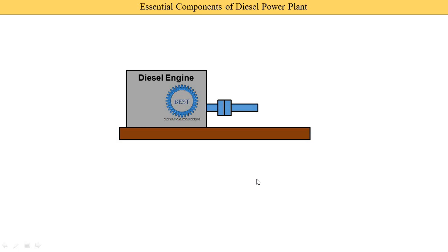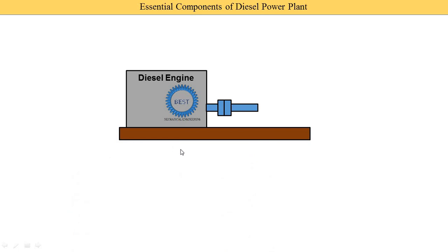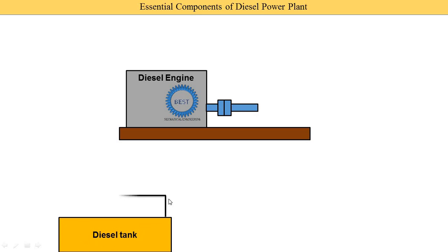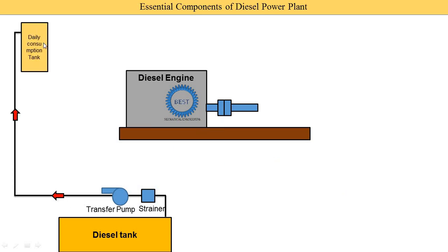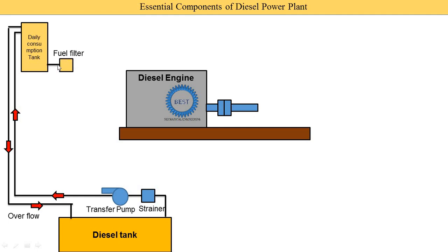The second system is the fuel supply system. The diesel is first supplied from the main diesel tank to the strainer, then to the transfer pump. The transfer pump supplies diesel into a daily consumption tank. If the daily consumption tank overflows, the diesel is supplied back to the main diesel tank. From the daily consumption tank, a fuel filter removes impurities and dust particles from the diesel, and then the diesel is supplied to the fuel injector.